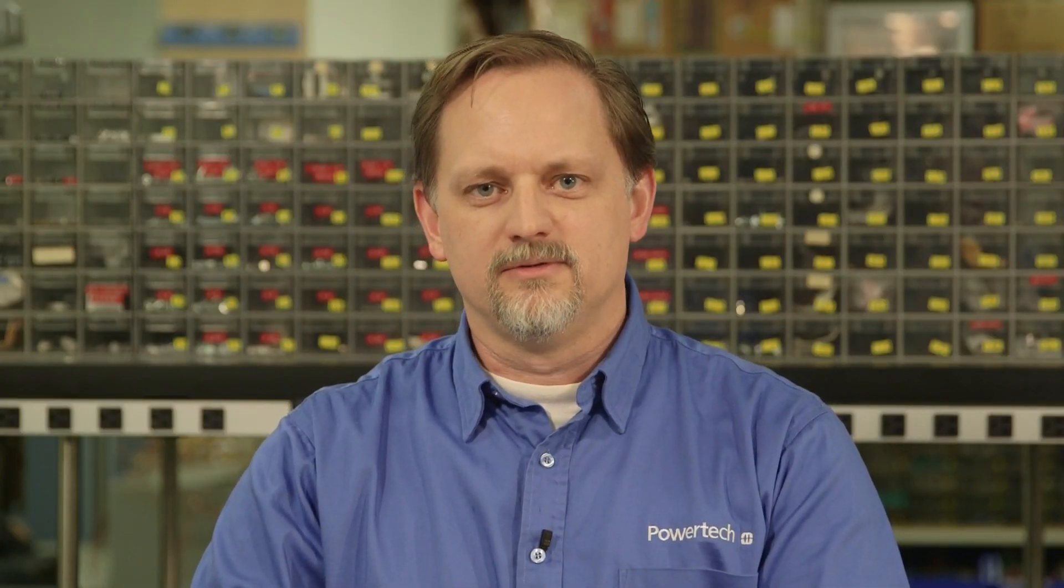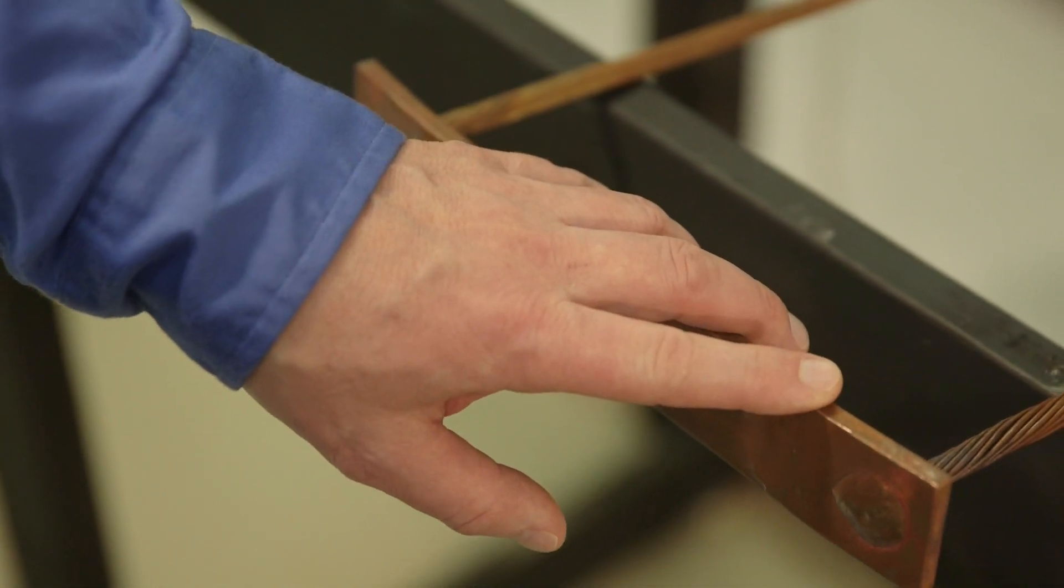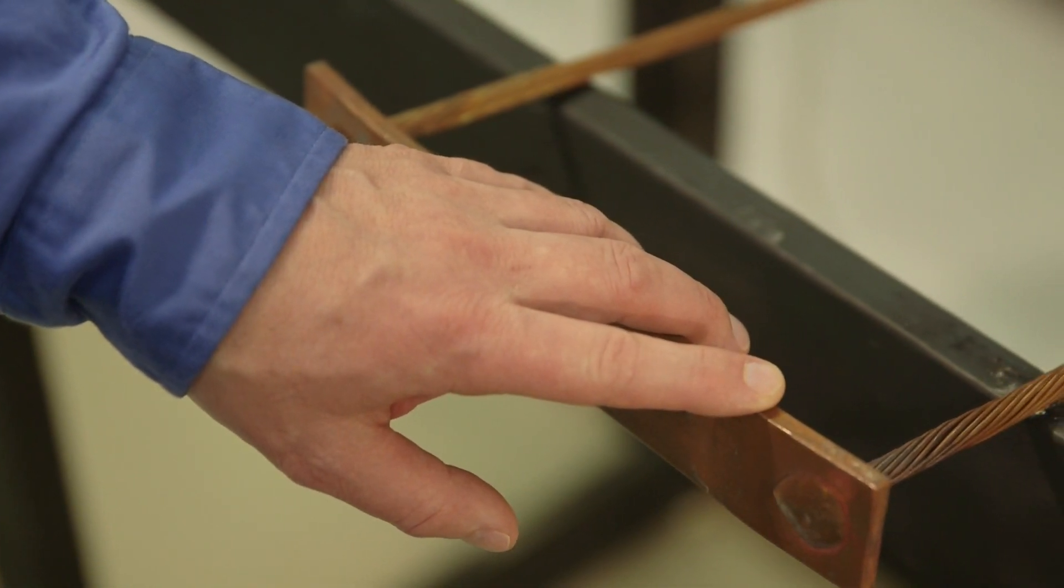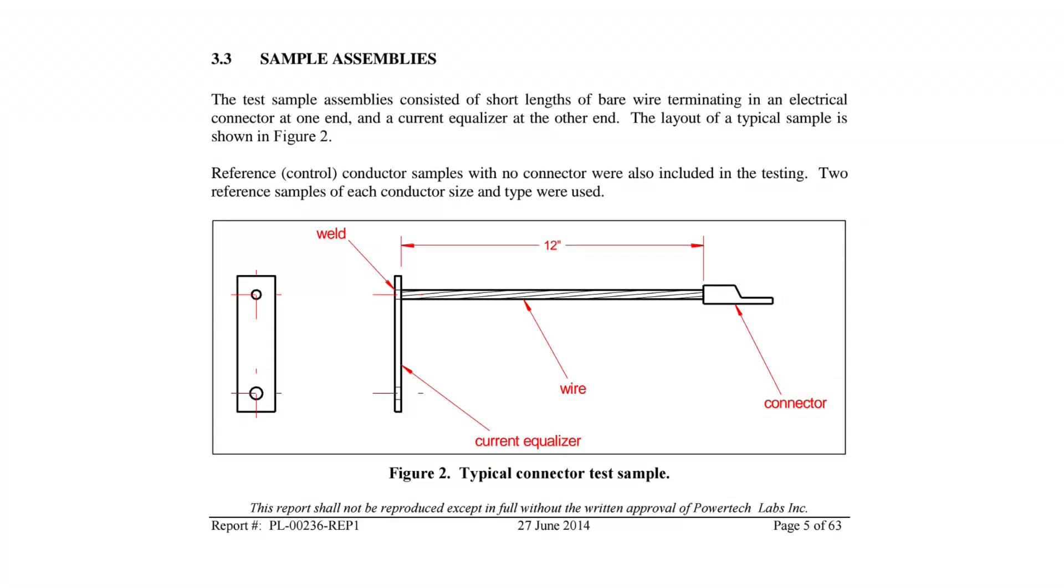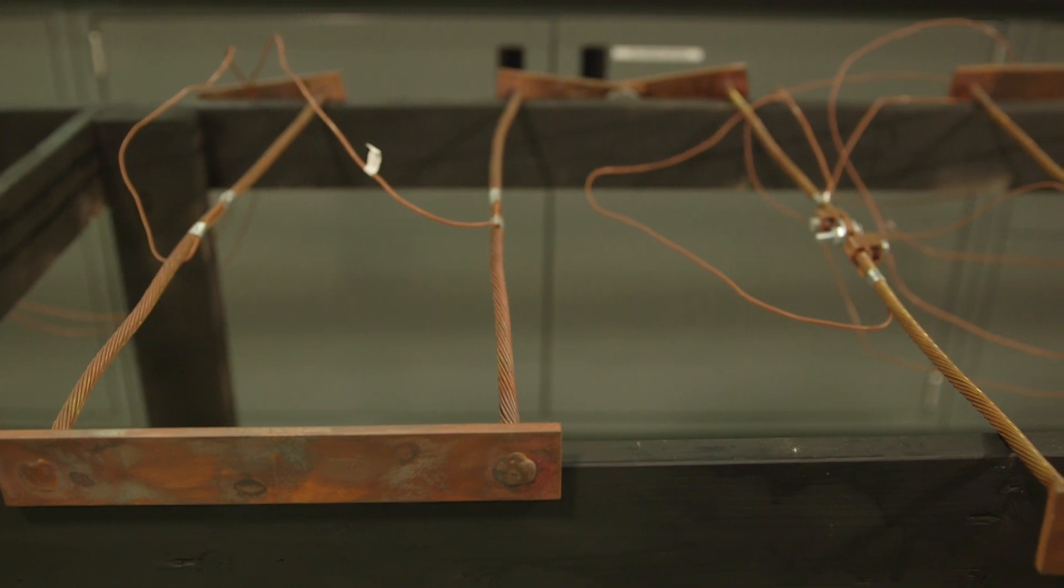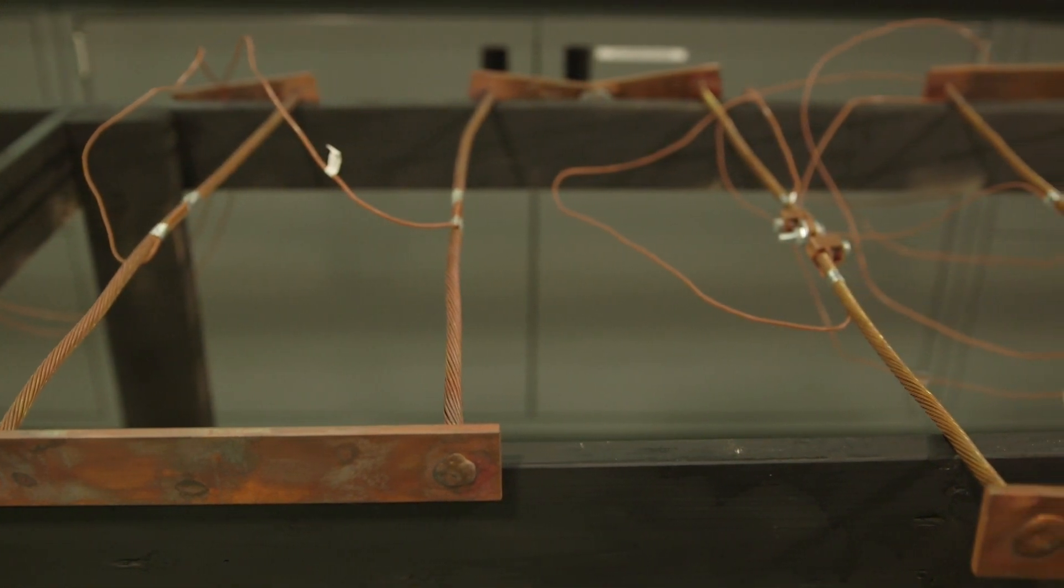Current equalizers were installed on the end of each test sample. A current equalizer consists of a conductive bar that is welded to all strands at the end of the conductor. This is a standard technique and ensures the best possible connection to the end of the conductor. Control samples were also prepared which consisted of lengths of conductor with equalizers but no connector.